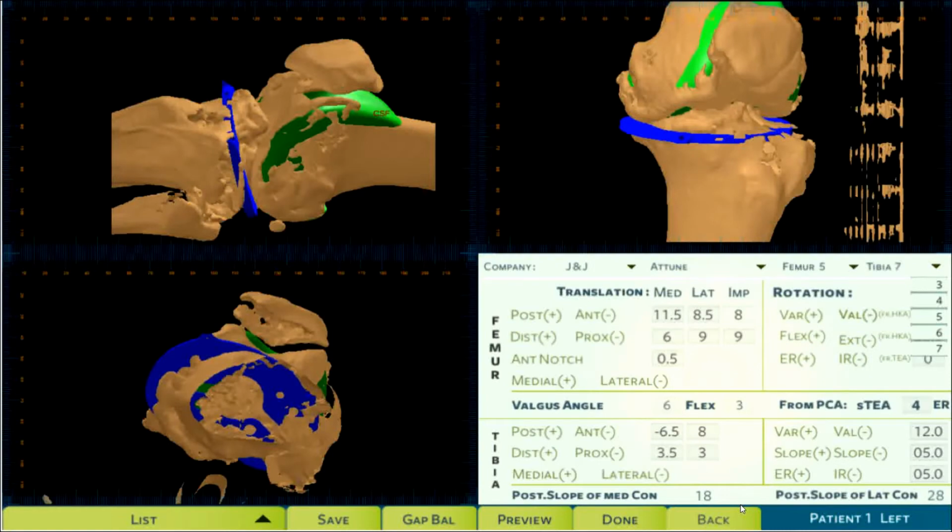The sizes of the femur and tibia are calculated on the basis of anatomic landmarks selected. The femur and tibia sizes can be changed according to the fit. The sizes of the tibia available will be dictated by the size of the femur selected, and hence only allowable sizes by the company will be displayed.